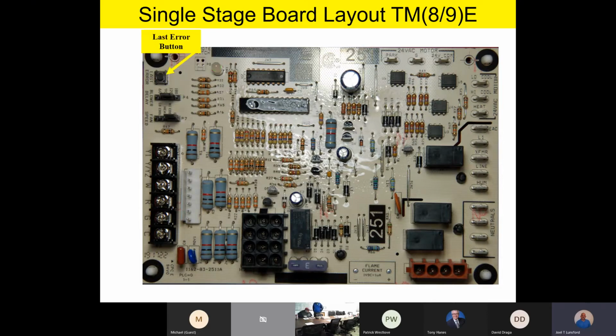Okay, we have a last error button right above our jumper selections. Team, what this does is allow you to go in and retrieve errors off the board. It should be noted that if you depress the last error button, you can start cycling through the last 5 errors on the board, so it will actually remember the last 5 errors. In addition, if you hold that button down for about 10 seconds, it'll clear the memory. Oftentimes service technicians like to clear that memory so that if there are any fresh faults on the board, they can come in and read those at a later date. So that last error button allows you to look at the last 5 errors it remembers, and it also allows you to clear that memory if you hold the button down for about 10 to 15 seconds.